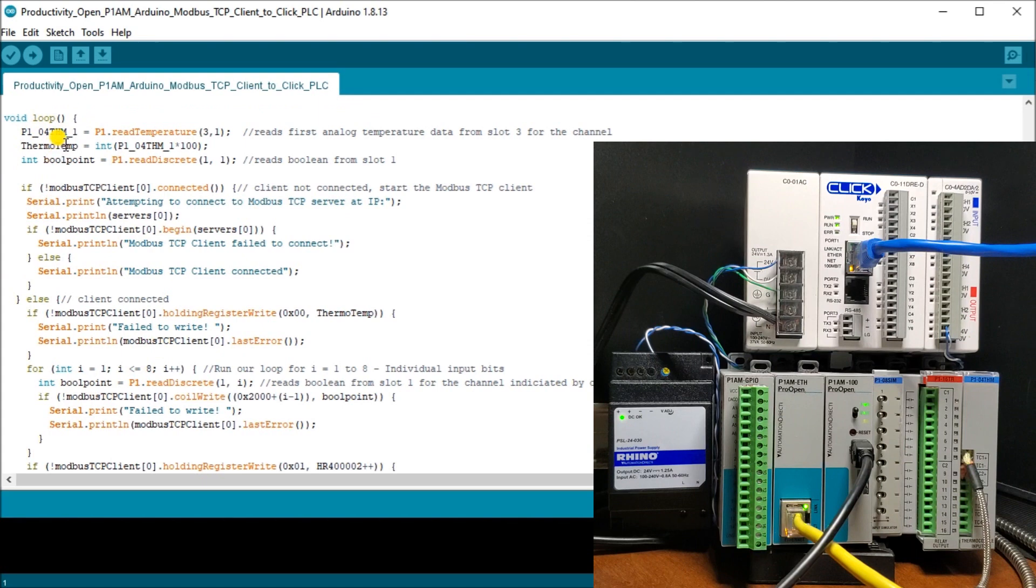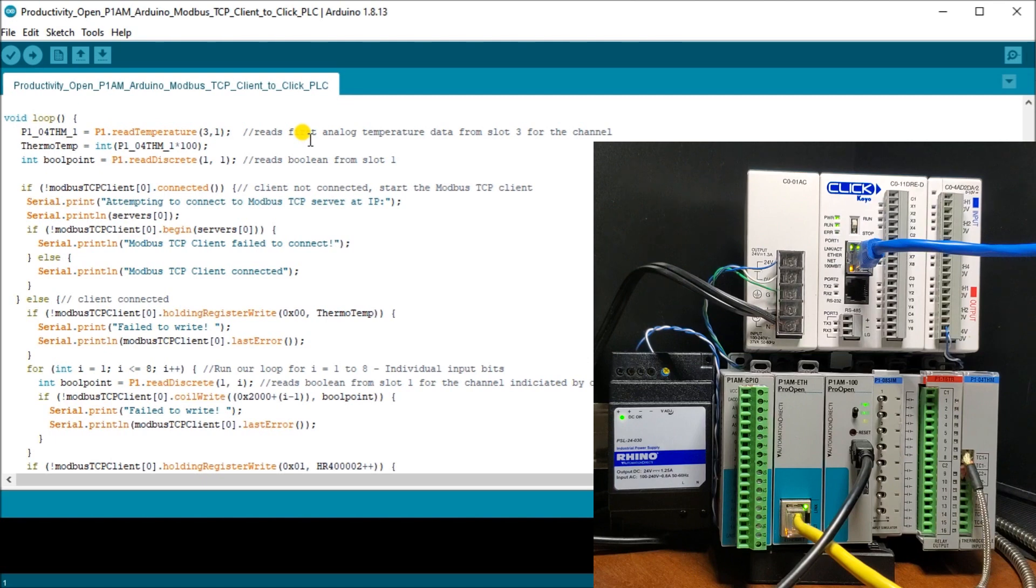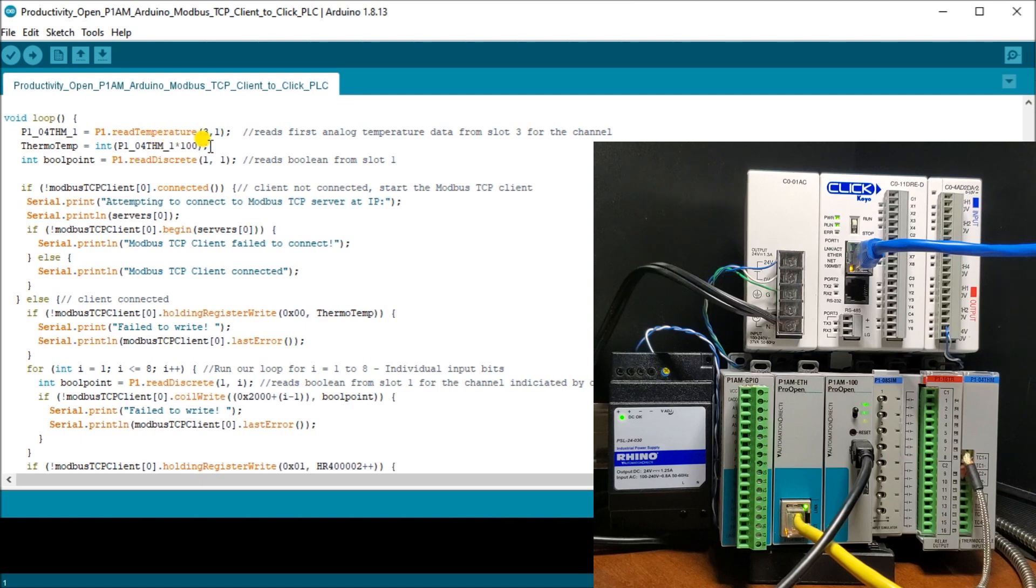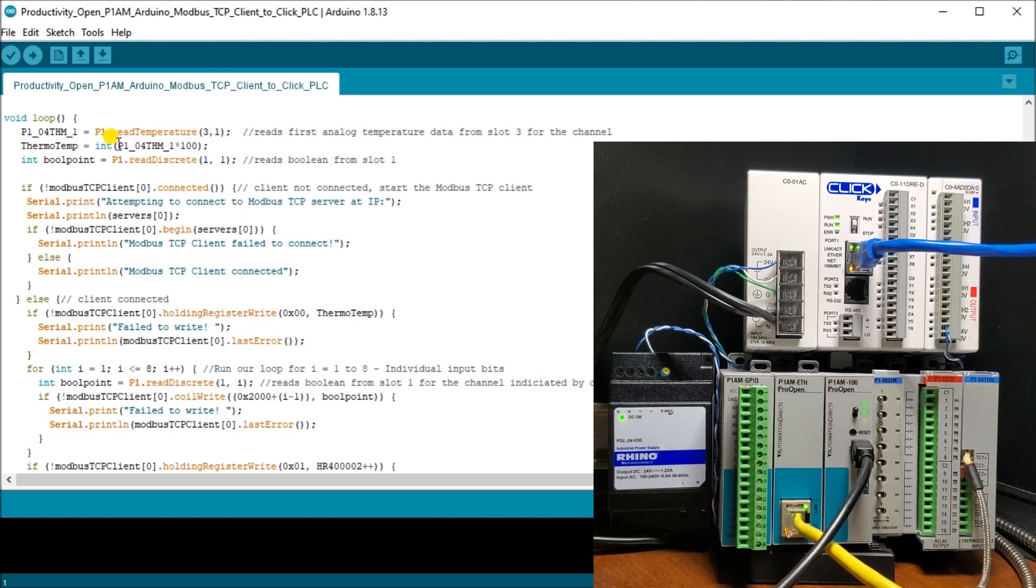So the first thing we do is we get our thermocouple input. It reads the first analog temperature data from slot three for the channel. Then we take a thermocouple or thermocouple temp and we convert that into an integer. So we take our temperature, which is a double, we times it by 100. So it gives me the two decimal places and then we change that into an integer. So now I have a four digit number that I'm going to be sending to our Click PLC.